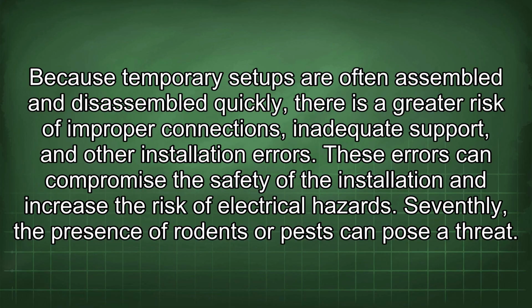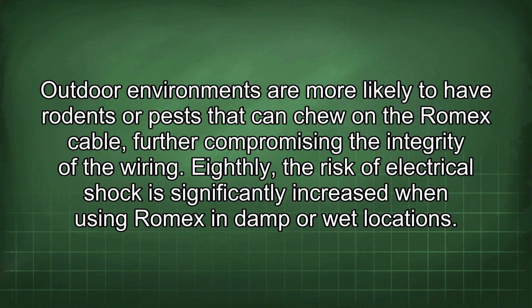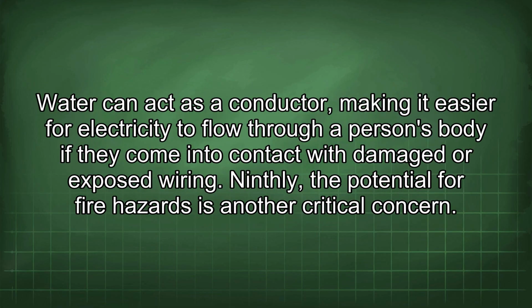Seventhly, the presence of rodents or pests can pose a threat. Outdoor environments are more likely to have rodents or pests that can chew on the Romex cable, further compromising the integrity of the wiring. Eighthly, the risk of electrical shock is significantly increased when using Romex in damp or wet locations. Water can act as a conductor, making it easier for electricity to flow through a person's body if they come into contact with damaged or exposed wiring.